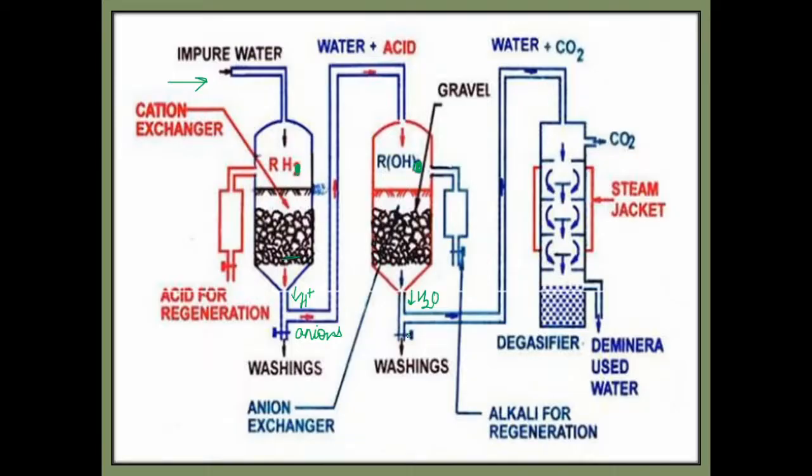But then if you want to use this water in boilers, maybe in other industry purposes wherein you need to have extremely pure water, then the third addition to this could be a degasifier. De means removal of gas. So the container which is used to remove the dissolved gases. Yes, you heard it right, dissolved gases. That means if the water here contains gases like dissolved oxygen, carbon dioxide, etc., we can remove those dissolved gases also at the end using a degasifier.